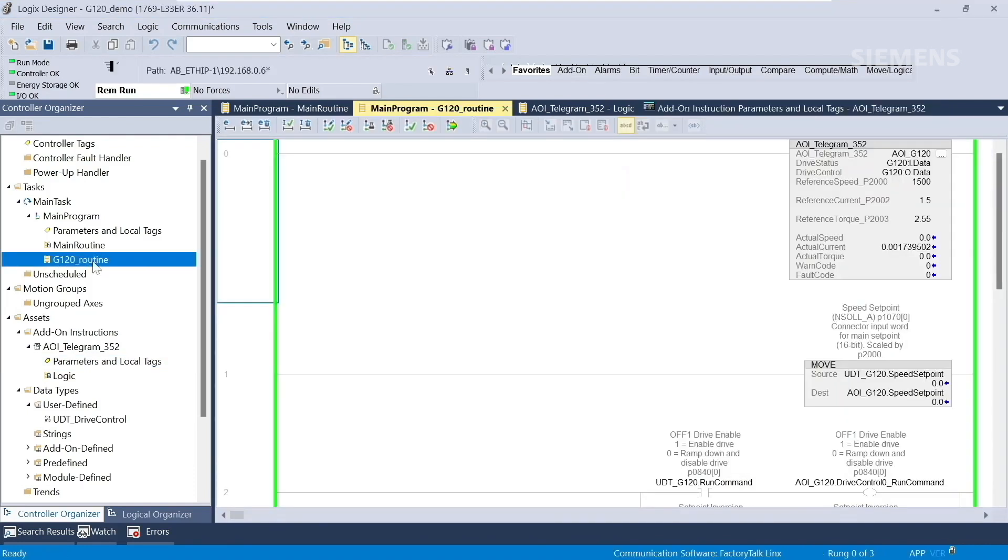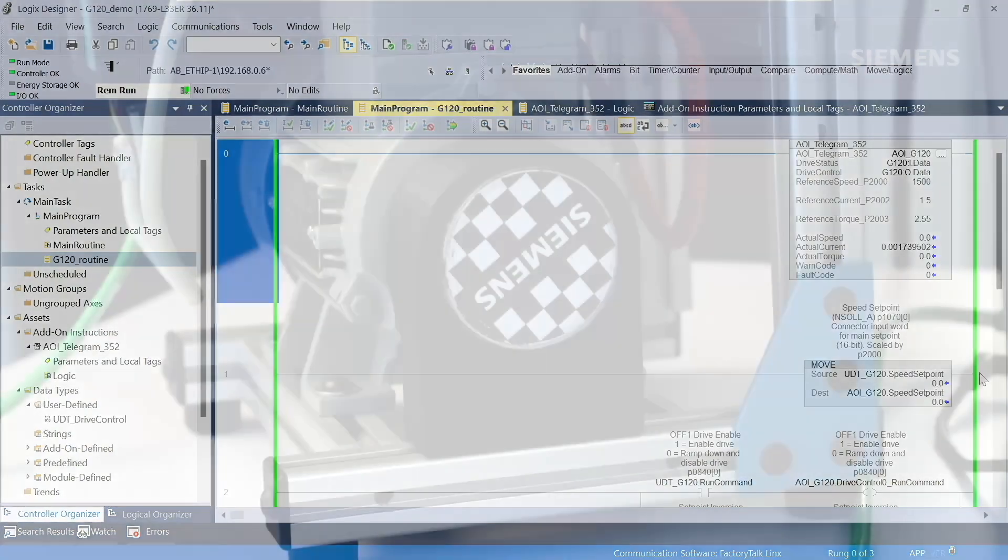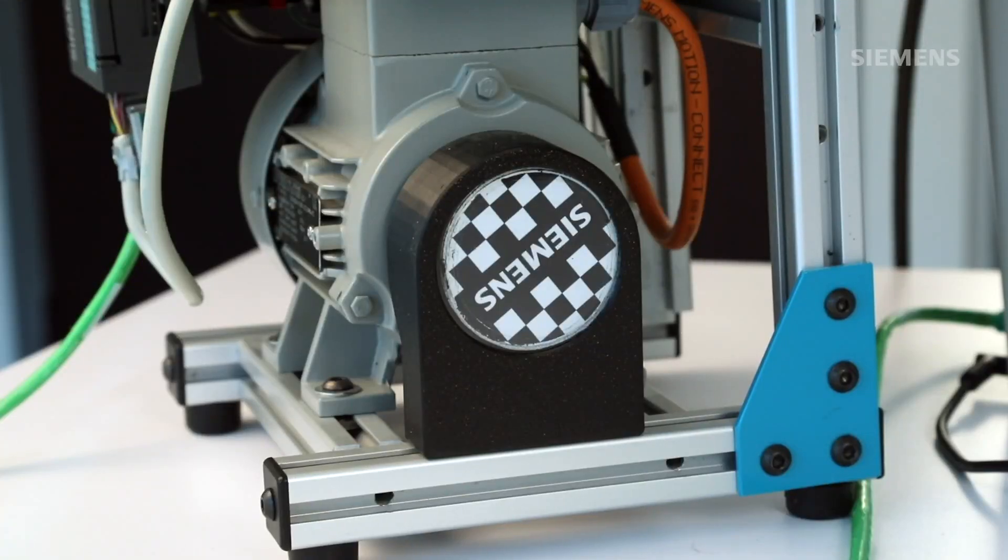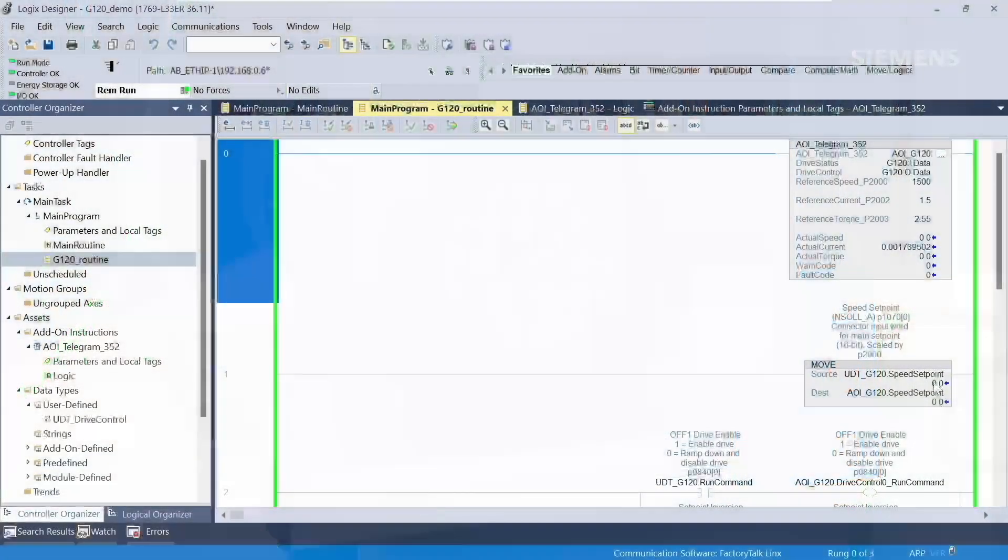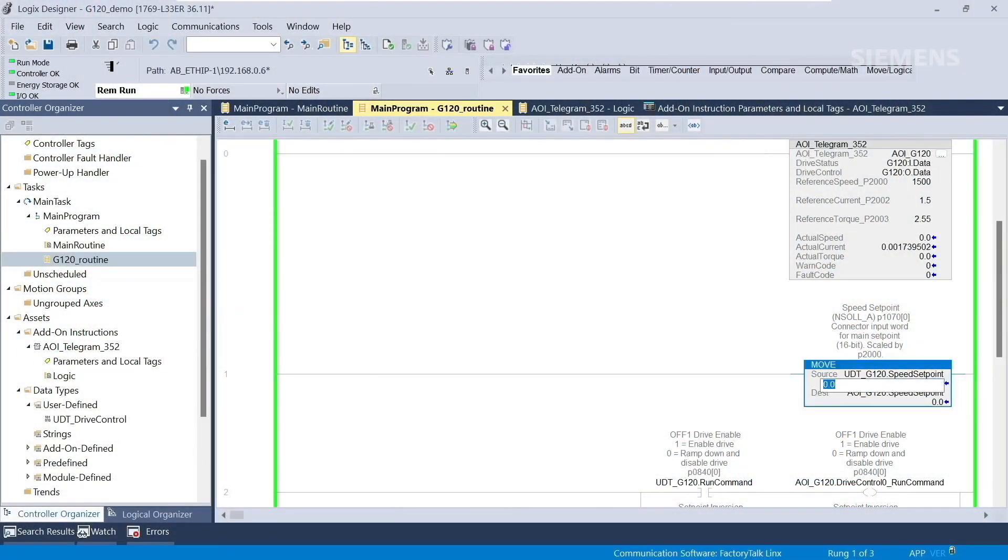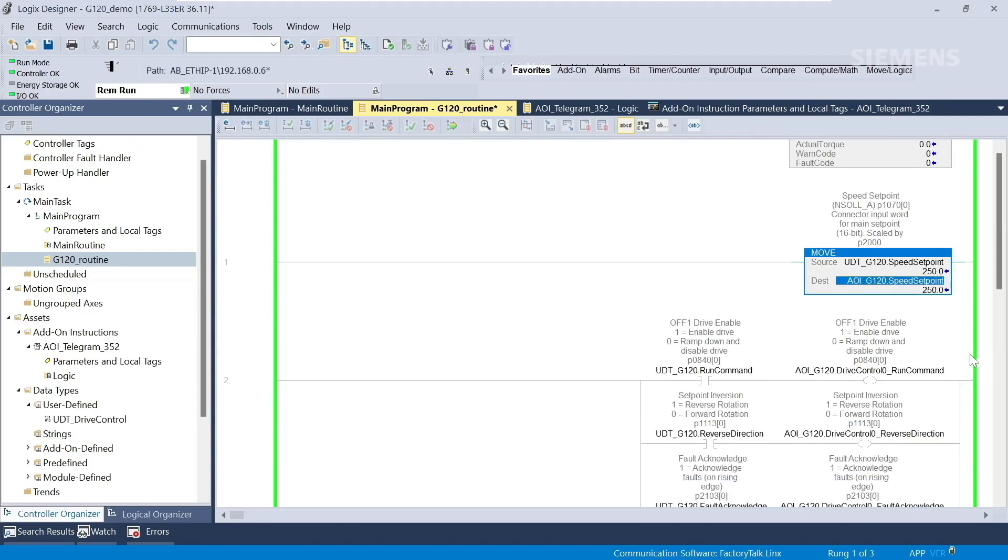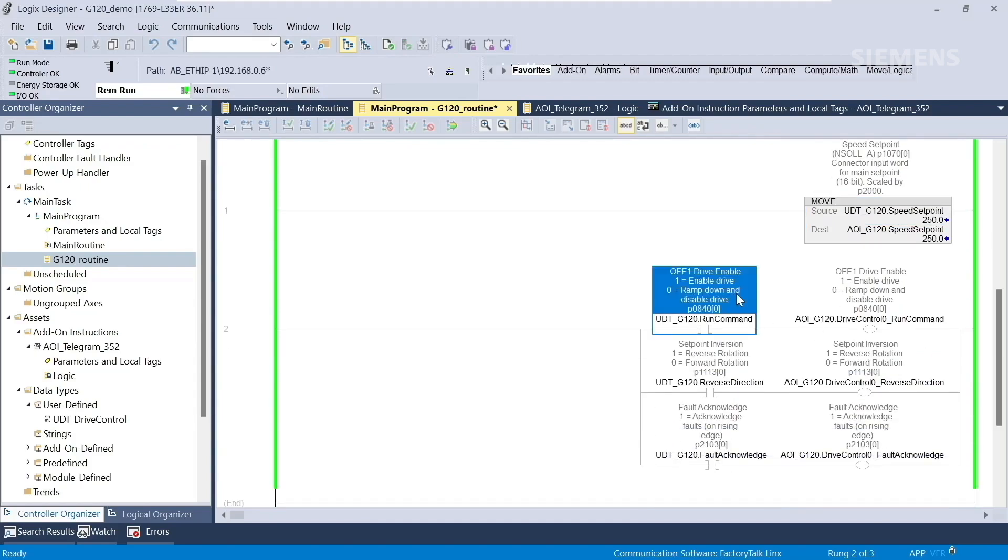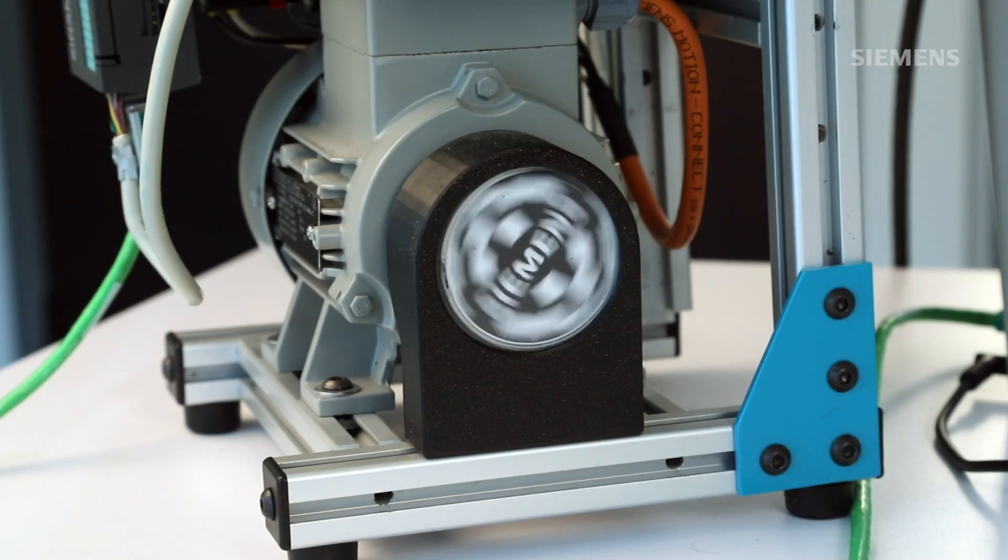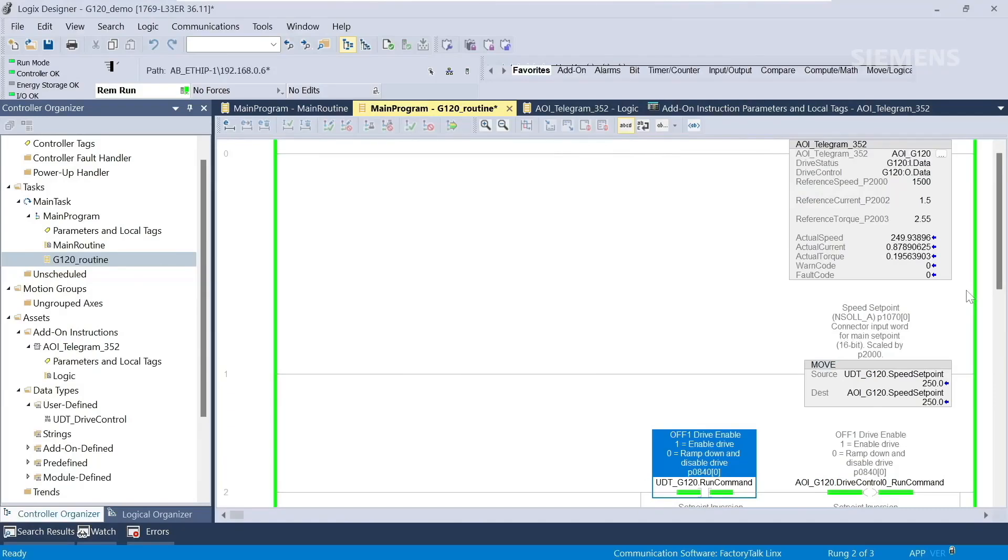I'm going to go back to the G120 Routine. The values displayed in the AOI block show the actual speed, current, and torque as zero, which makes sense because the motor isn't turning. To get this motor moving, we'll set our speed setpoint to 250 RPM and send a run command. Now you can see that the motor is turning and being controlled by the CompactLogix PLC. You can also see that the AOI block is displaying the actual speed as 250 RPM.